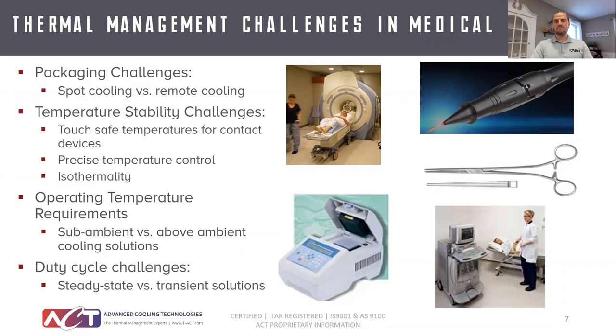Medical devices covers a wide range of different products and applications. There's no one specific solution for a medical device. The systems come in very small sizes like surgical devices to very large machines like MRI machines, so packaging challenges are really what's unique about medical devices. Sometimes there's not enough space immediately around where the heat generating component is to dissipate the energy required, so you need to move that heat to a location where cooling is available. Temperature stability challenges are also unique — oftentimes precise temperature control is required. For surgical devices, very precise temperature for cutting tissue is needed so as not to exceed certain values and damage the tissue.